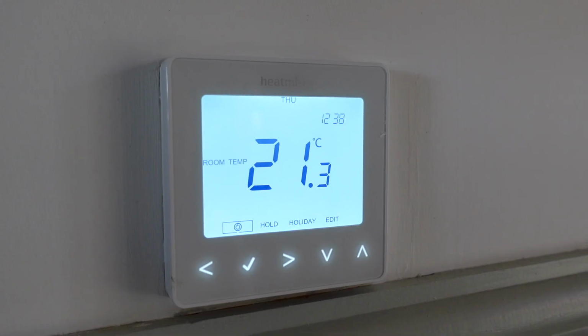I see. So we're going to still keep our thermostats for the underfloor heating. Those will still call for heat, or are we? We could keep the stats and the actuators. We're not going to get the underfloor talking to the heat pump. The underfloor is not going to tell the heat pump what it's doing. Okay. There's no on and off control. I suggest we remove some of the actuators to the majority of the main areas in the property. We could still leave the hallway and the cloakroom. That can still be controllable. Let's say we're going to try and make about 50% of the actual underfloor manifold fully open path.